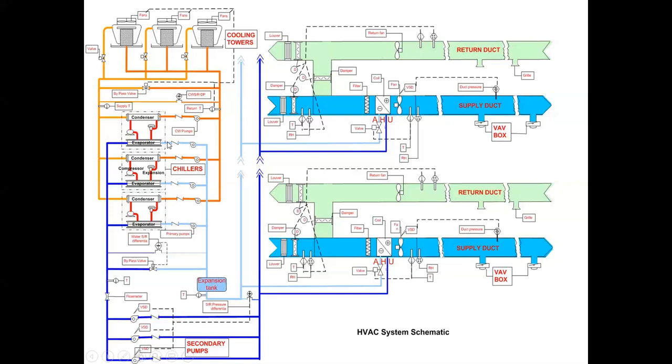Then we're going to cool it down. We're shooting for a 10 to 12 degree delta T on the chiller. So if we're 42 out of the chiller at full load, we're looking at probably a 12 degree delta T, so 52, 54 on the return. And that's an issue. You can't load a chiller if you can't get warm water back to it. A lot of systems have a problem called the low delta T problem on chillers. That'd be another good YouTube video for me to send. I've got a lot of work to do on YouTube, don't I?